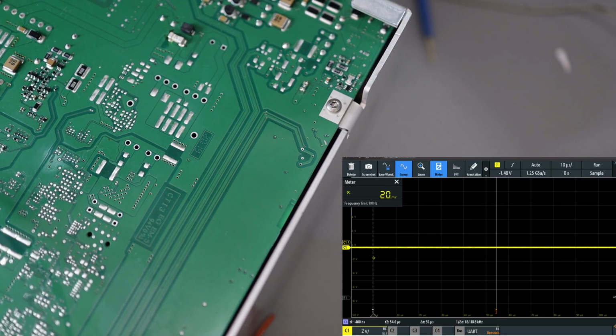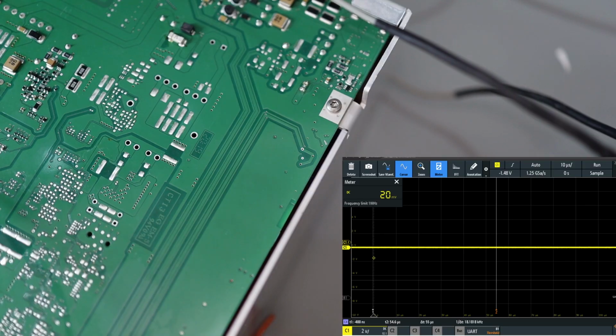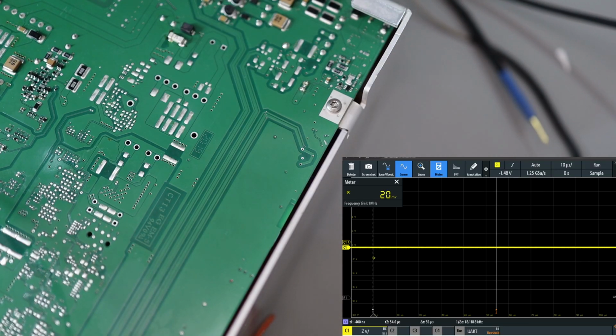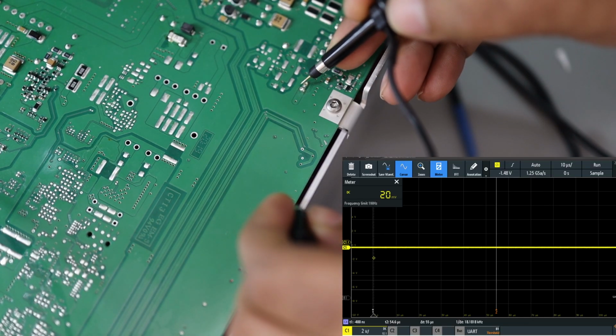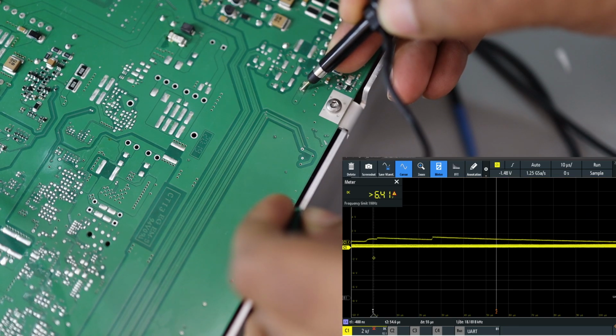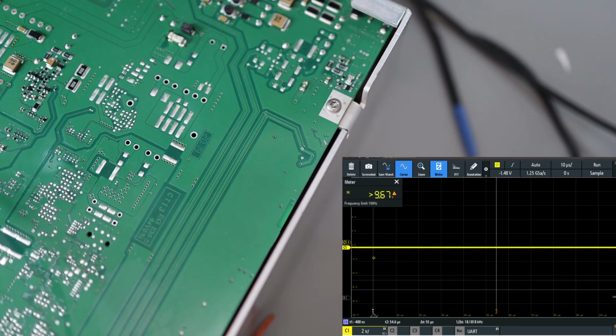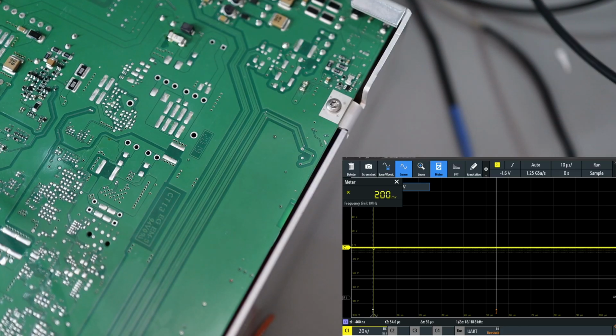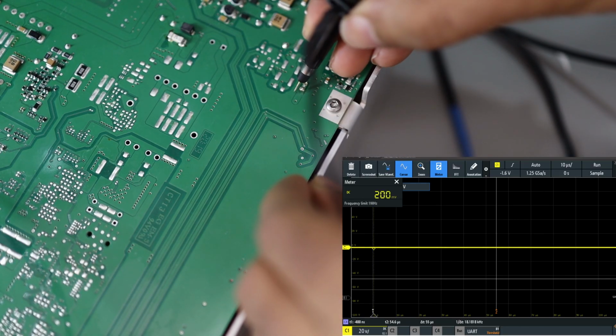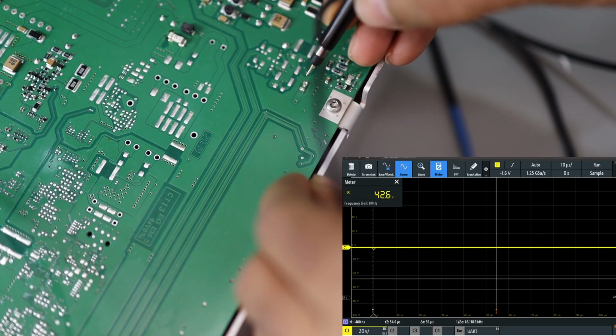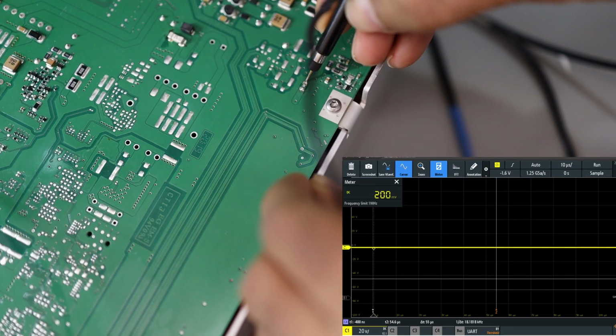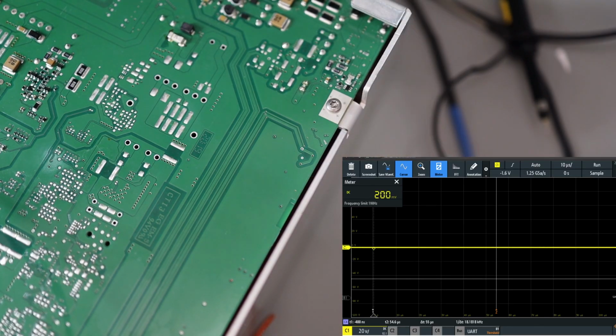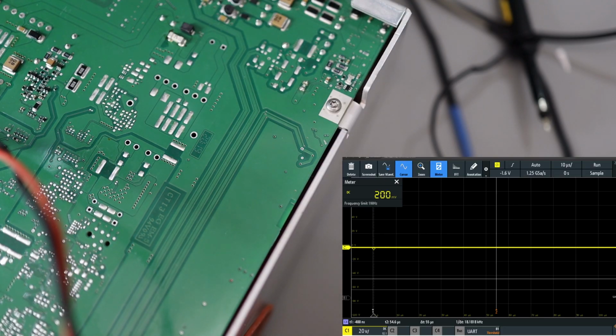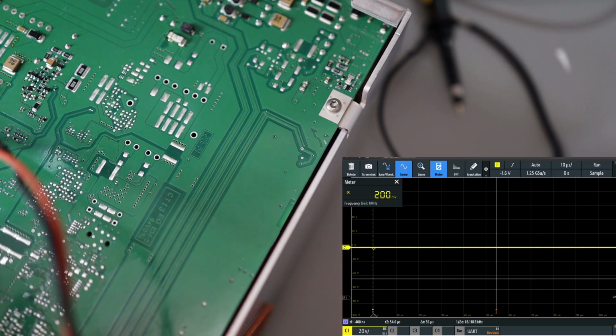If you want to measure the voltage, I'll turn on the instrument and I'll show you with my multimeter. I'll show you with the oscilloscope itself. It's the unisolated side, so it says greater than 10 volts because the time base is quite big. It says 42 volts, which is what I'm feeding in, and here it says, of course, 0 volts because the fuse is blown. So that's it. We'll repair this fuse. Most likely we will get the instrument up and running once the power is established. This thing will start to work.